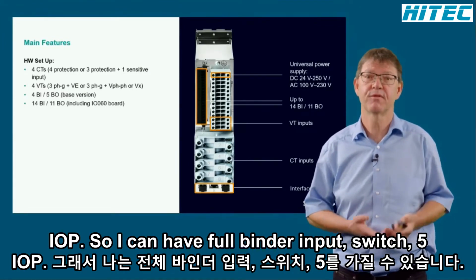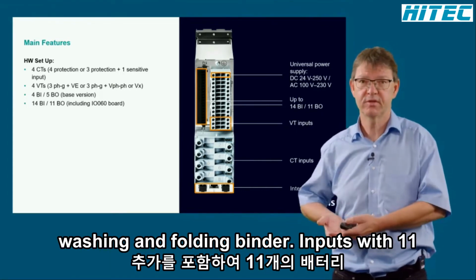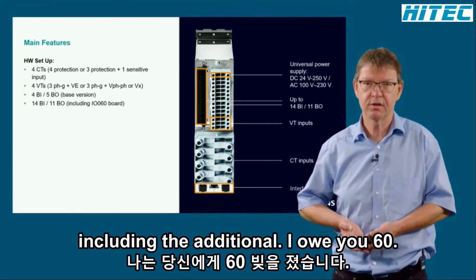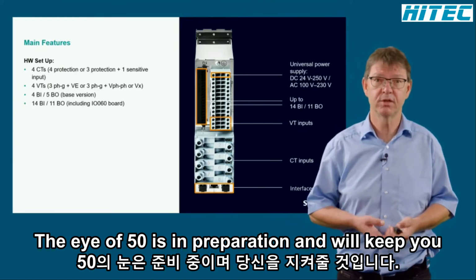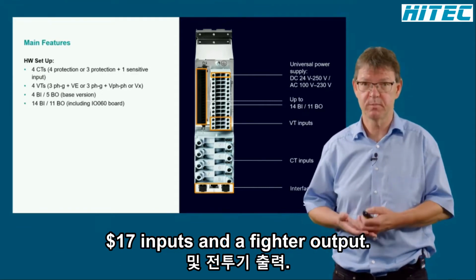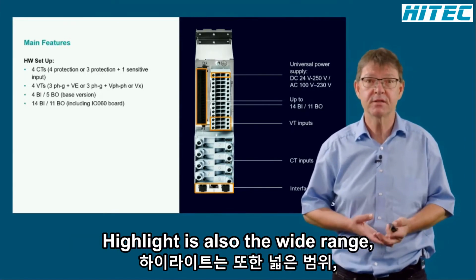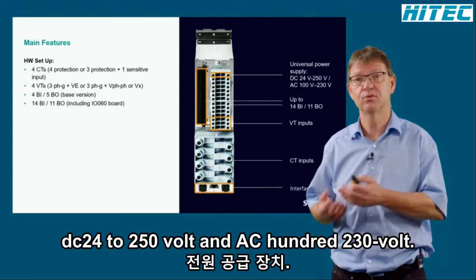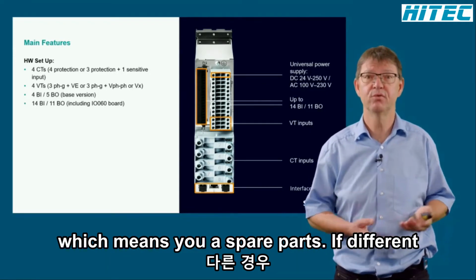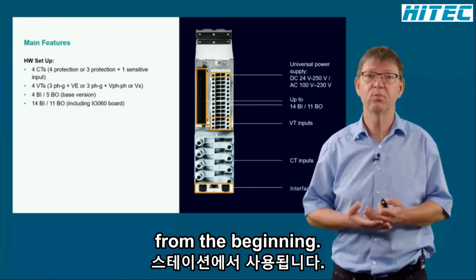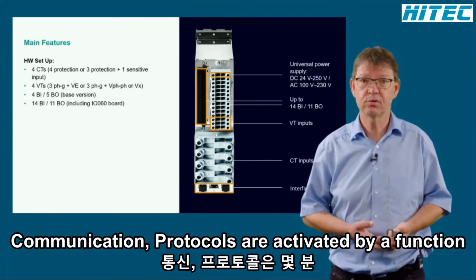So you can have 4 binary inputs with 5 binary outputs in the base version and 14 binary inputs with 11 binary outputs, including the additional I/O card, the so-called IO60. Another I/O card, the IO50, is in preparation and will give you in total 17 binary inputs and 8 binary outputs. These optional I/O cards need to be ordered right from the beginning. A highlight is also the wide-range power supply for all voltages, DC 24 to 250 volt and AC 100 to 230 volt. This reduces variance, which means fewer spare parts if different auxiliary voltages are used in the various substations. Finally, the interfaces are always on board right from the beginning. Communication protocols are activated via function points, about which we give some information in a few minutes.